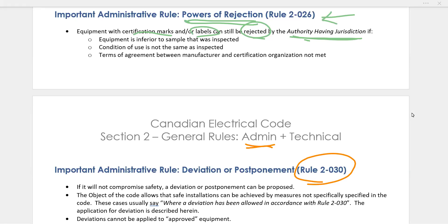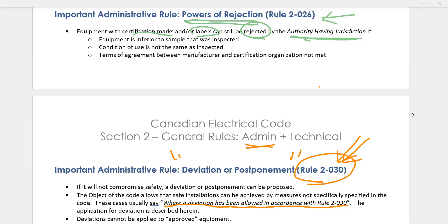The last administrative rule in Section 2 is Rule 2-30, called Deviation or Postponement. Throughout the code you'll see phrases like 'a deviation has been allowed in accordance with Rule 2-30.' This rule acknowledges that the code doesn't cover every situation. There are safe situations not covered in the Canadian Electrical Code, and that doesn't mean you cannot proceed — it means you have to apply for a deviation according to your situation, but only if the situation won't compromise safety.